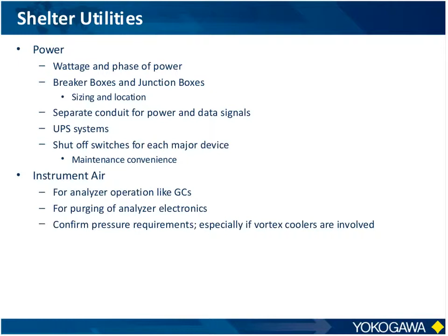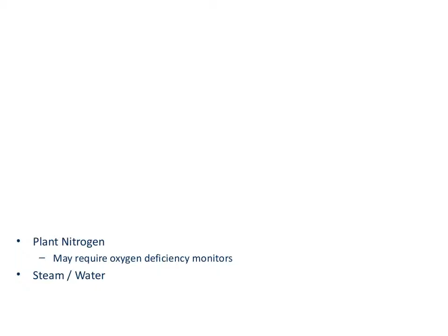So all this needs to be defined as part of the total package and total solution. Instrument air. A lot of the analyzers use plant instrument air or plant nitrogen for heating of their internal ovens or purging of their systems. So these requirements, as far as the amount of volume and the amount of pressure required, need to be defined and built into the design of the system. I talked about the plant nitrogen, but there might be steam, for example, if you have to heat the sample systems to keep the sample nice and hot so it doesn't condense.